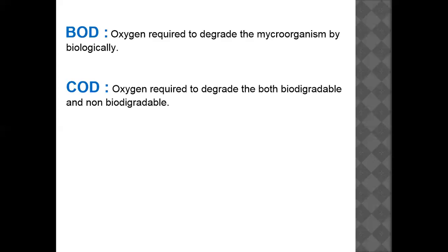BOD means biological oxygen demand, and COD means chemical oxygen demand. COD is the amount of oxygen needed to chemically oxidize the wastes. In COD measurement, both biodegradable and non-biodegradable substances are chemically oxidized. As a result, the COD value is always greater than the BOD value.